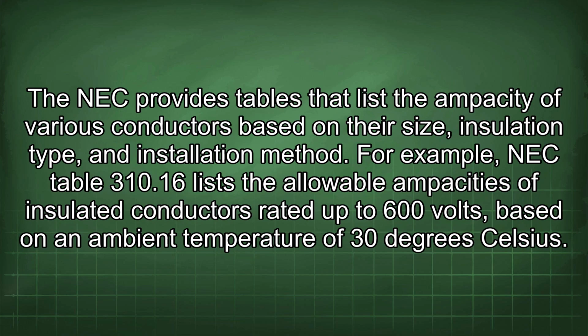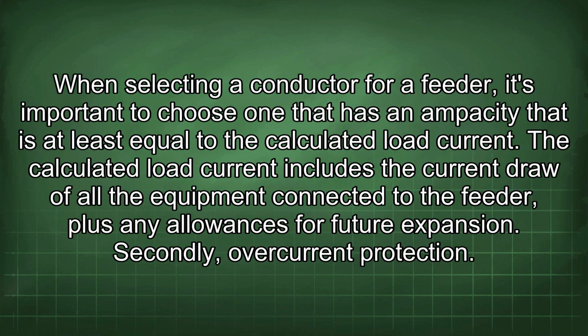The NEC provides tables that list the ampacity of various conductors based on their size, insulation type, and installation method. For example, NEC Table 310.16 lists the allowable ampacities of insulated conductors rated up to 600 volts, based on an ambient temperature of 30 degrees Celsius. When selecting a conductor for a feeder, it's important to choose one that has an ampacity that is at least equal to the calculated load current. The calculated load current includes the current draw of all the equipment connected to the feeder, plus any allowances for future expansion. Secondly, overcurrent protection.